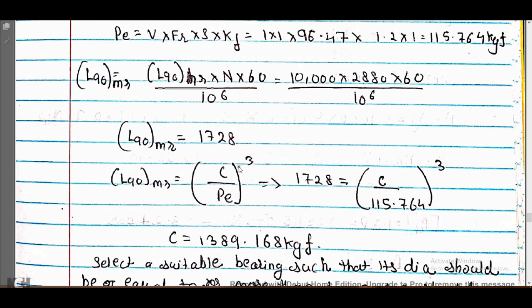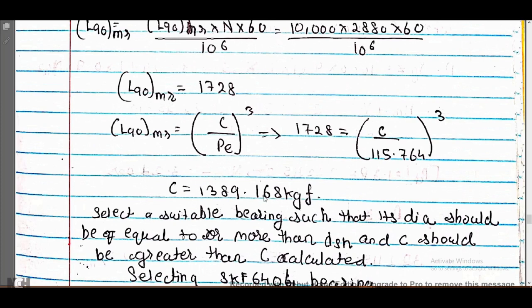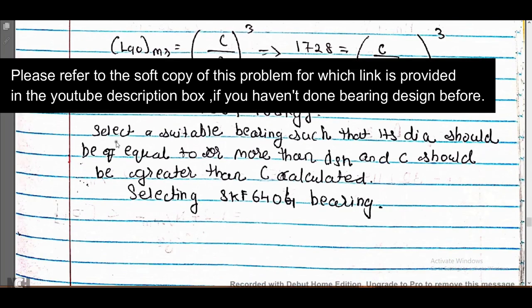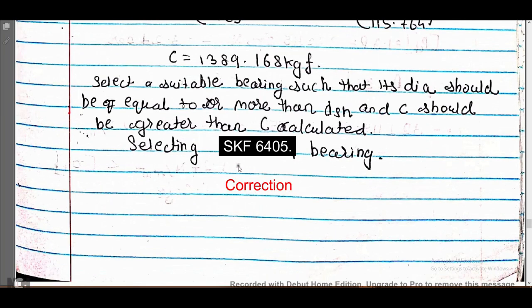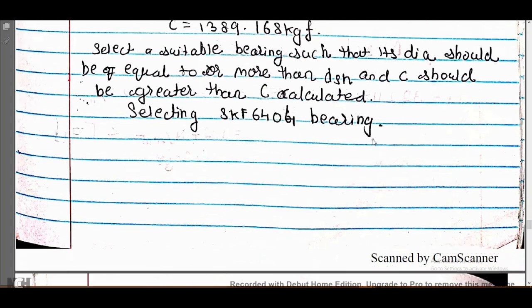Using the formula L90_mr = (C / P_E)³, we get C = 1389.168 kgf. We then select a suitable bearing such that its bore diameter is equal to or greater than D_sh and its dynamic load capacity C is greater than the calculated C. We select the SKF 6405 bearing.